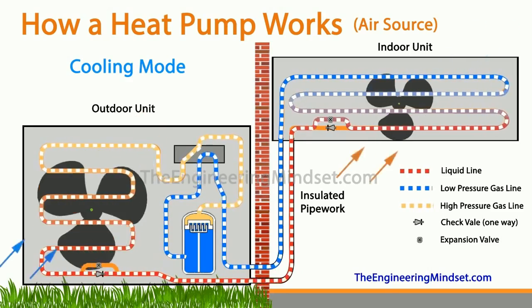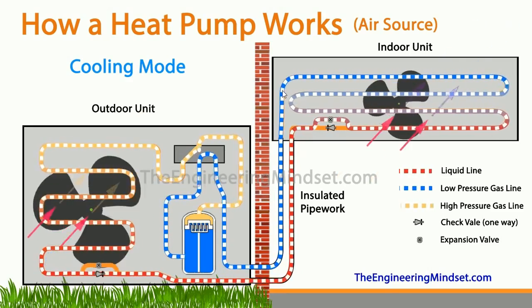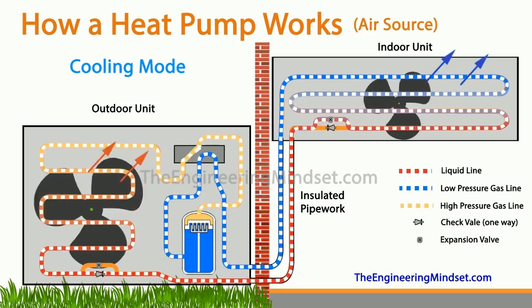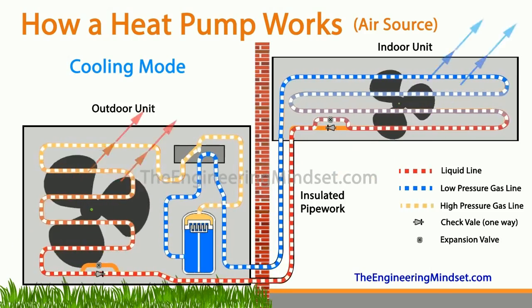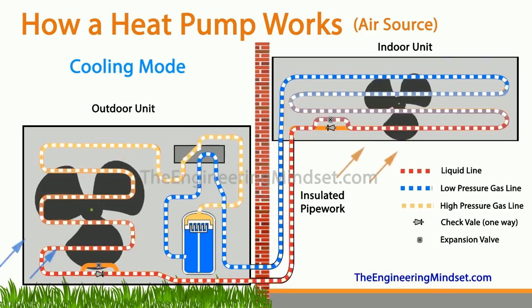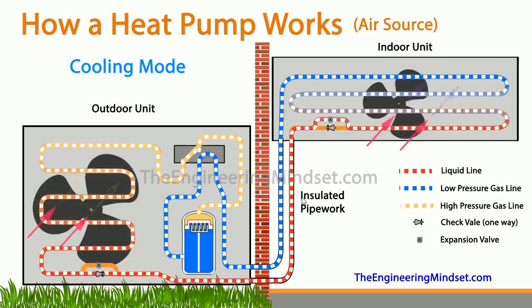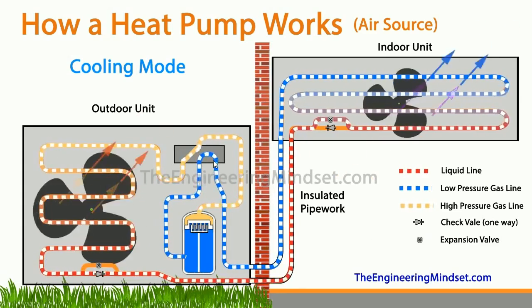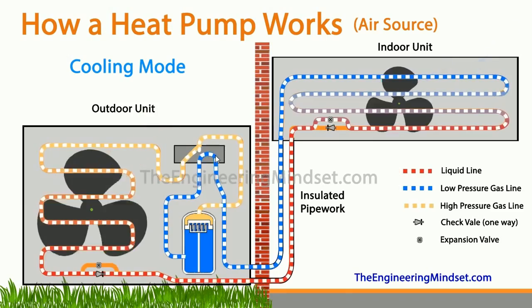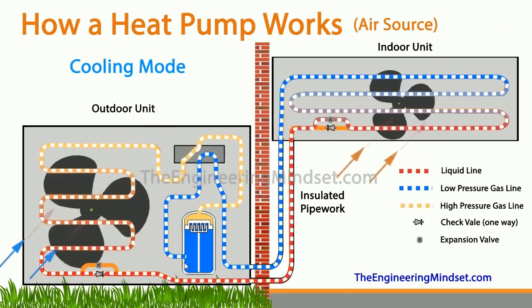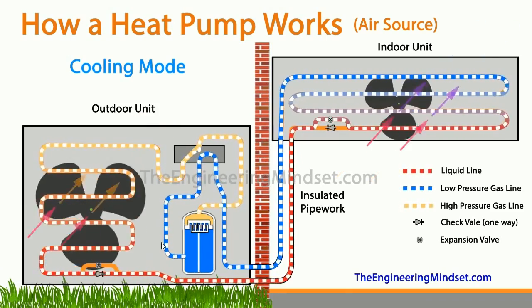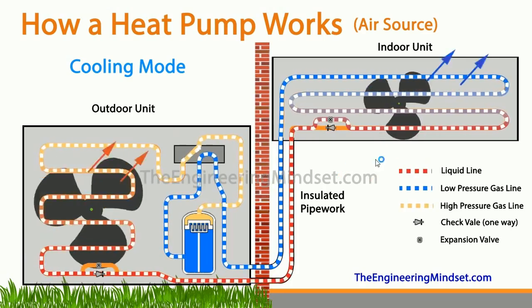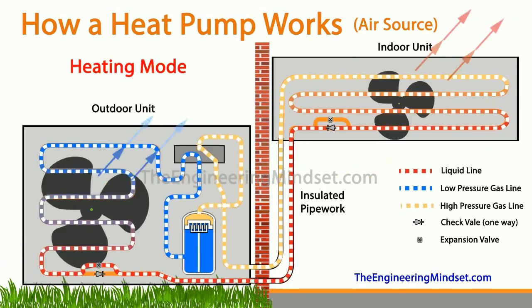So by the time the refrigerant passes through there and leaves the evaporator or the indoor unit, the refrigerant is going to leave as a low pressure, low temperature saturated vapor, and that's going to head straight back round into the reversing valve, which is currently set to divert the refrigerant off straight back into the compressor. And that refrigerant will then pass through the compressor and repeat the entire cycle.